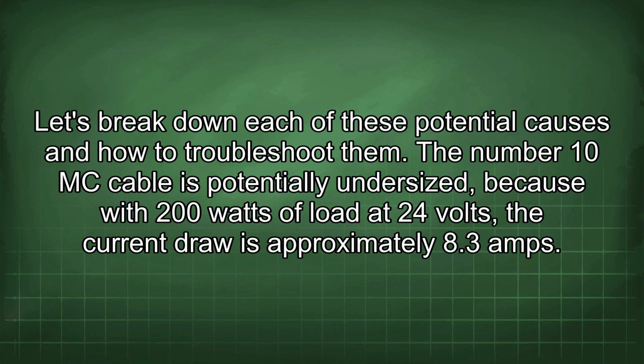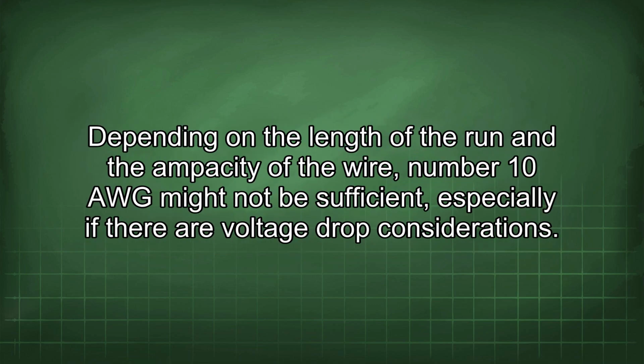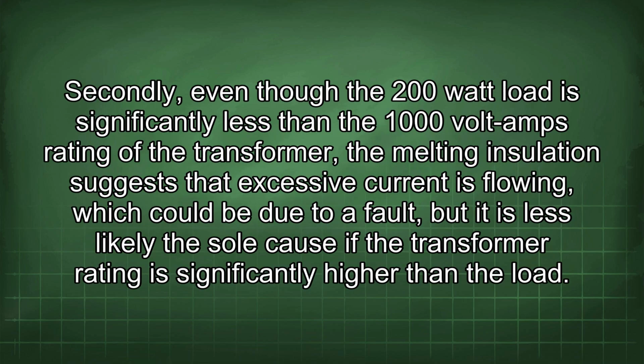The number 10 MC cable is potentially undersized because with 200 watts of load at 24 volts, the current draw is approximately 8.3 amps. Depending on the length of the run and the ampacity of the wire, number 10 AWG might not be sufficient, especially if there are voltage drop considerations. Secondly, even though the 200 watt load is significantly less than the 1000 volt amps rating of the transformer, the melting insulation suggests that excessive current is flowing, which could be due to a fault, but it is less likely the sole cause if the transformer rating is significantly higher than the load.